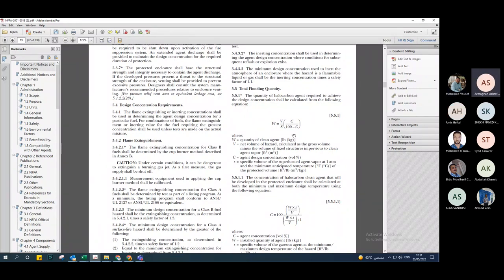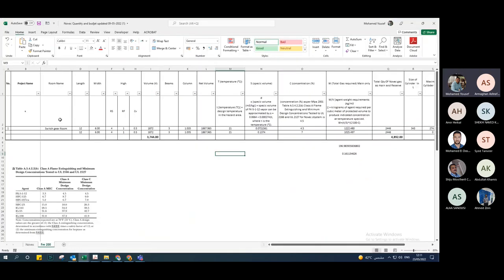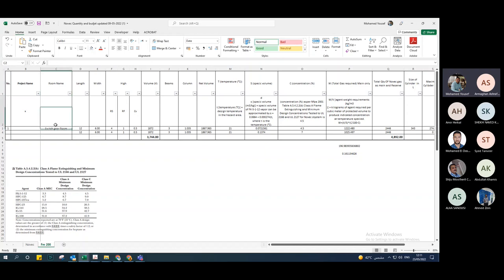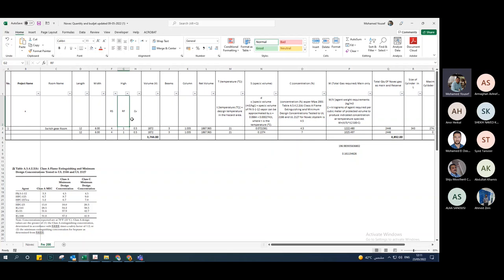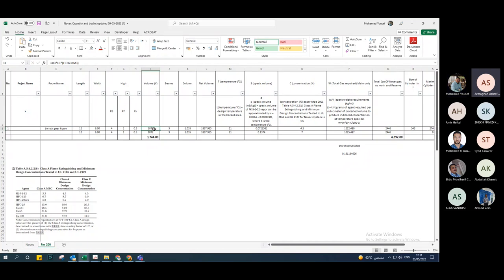To calculate the volume, you can initiate an Excel sheet with the project name, room name (such as communication room, switching room, or battery room), then input the length, width, and height of the room. If you have a raised floor or ceiling void, you must include all those volumes. The total volume equals length × width × height.